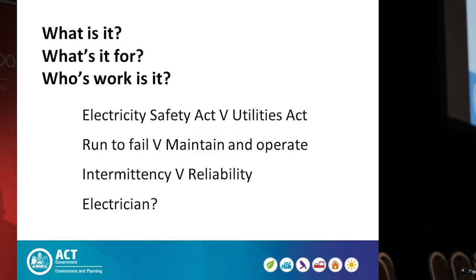So what was this thing when we started to build it? In the ACT, our Electricity Safety Act stops at the point of attachment or entry to an installation - everything else is a network under our Utilities Act. We regulate all utilities: water, gas, sewer, street lights, and soon other things under a separate act. So if it's not a utility, and it's got electricity, it's under AS 3000. Originally it was argued that a solar farm is neither - not actually an electrical apparatus within the meaning of the rules, because each individual panel only produces 34 volts, and therefore it's ELV, meaning I'd have no regulatory oversight.